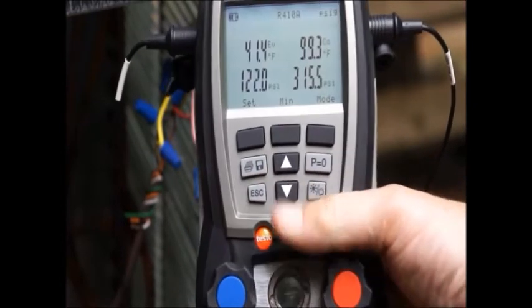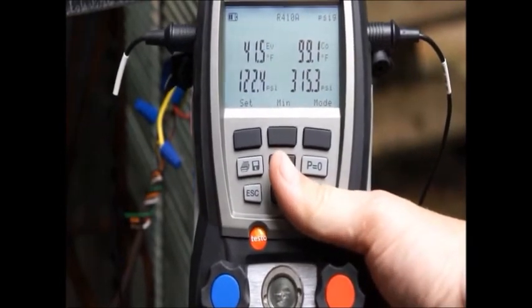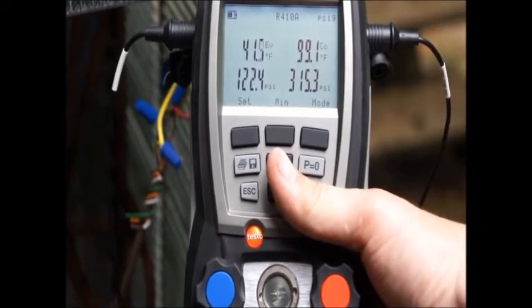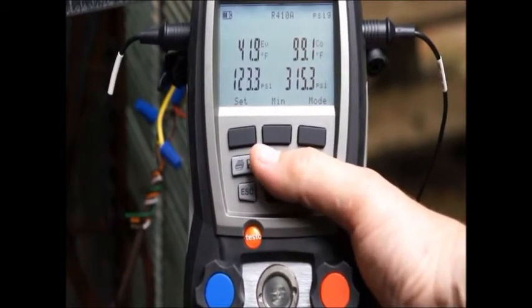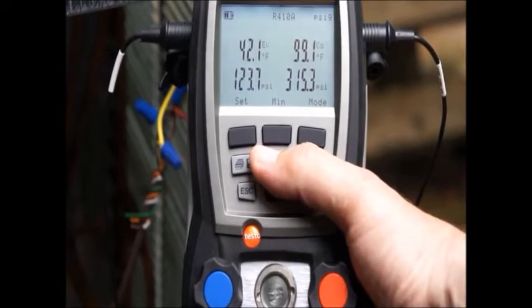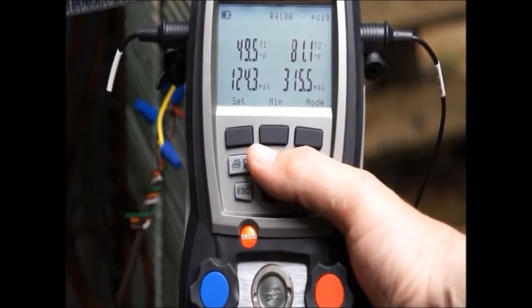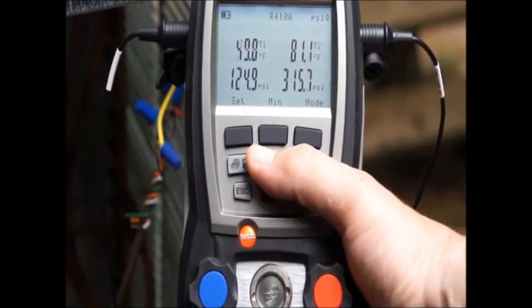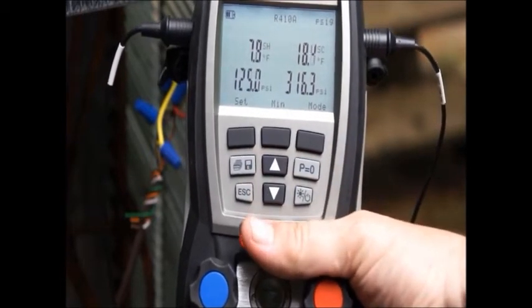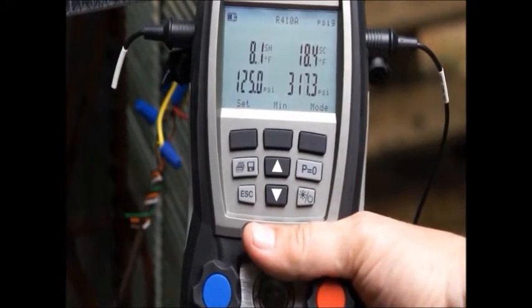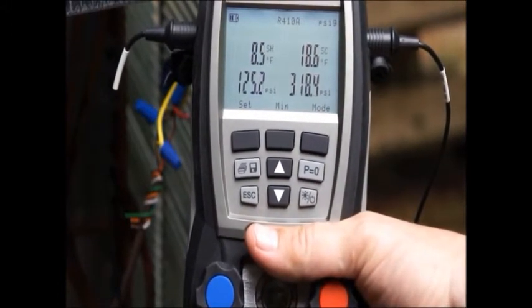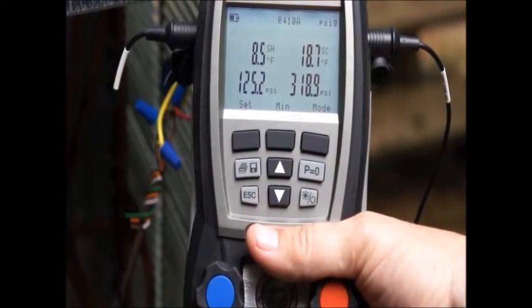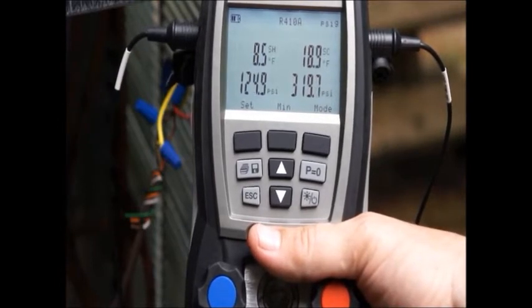Now I'm at 410A and you can see my evaporating temperature is 41.9 and my condensing temp is about 99. T1, T2 temperatures, superheat and subcooling. I'm running about 8.5 degrees of superheat and I just started this machine up.